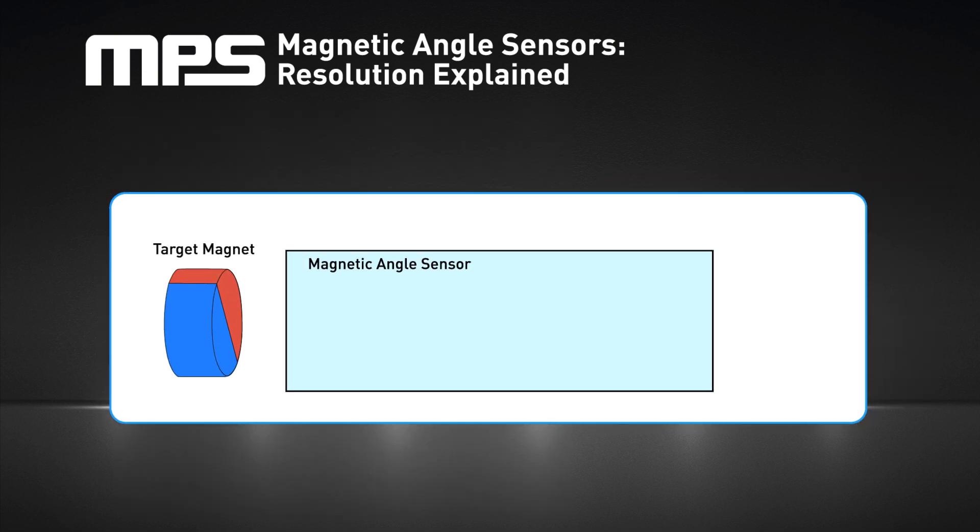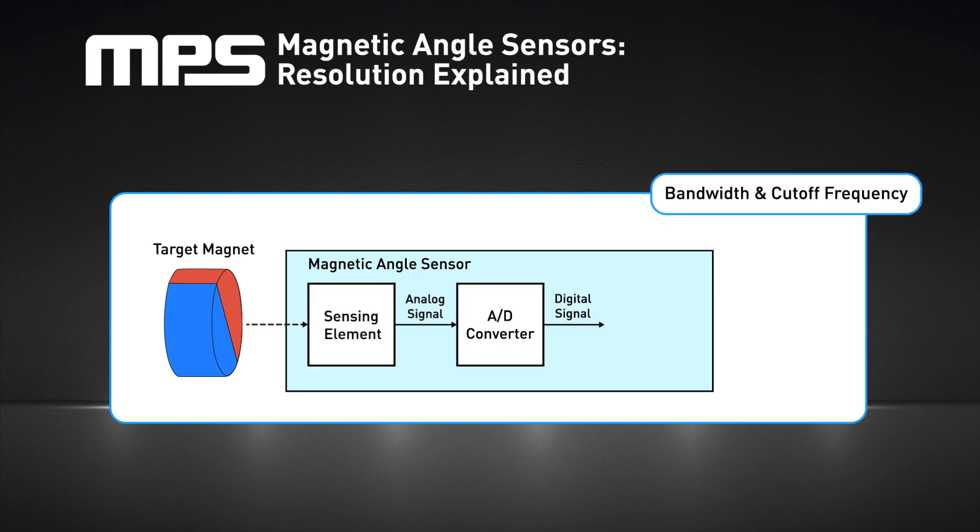When discussing sensor performance, a key parameter that is often overlooked is the bandwidth, also known as the cutoff frequency. Sensor bandwidth corresponds to a signal's frequency range, which can be measured by the sensor. Signals with a frequency larger than the sensor bandwidth are attenuated. A detailed characterization of the sensor would require its transfer function in an analytical or graphical form. At the bare minimum, the cutoff frequency should be provided.